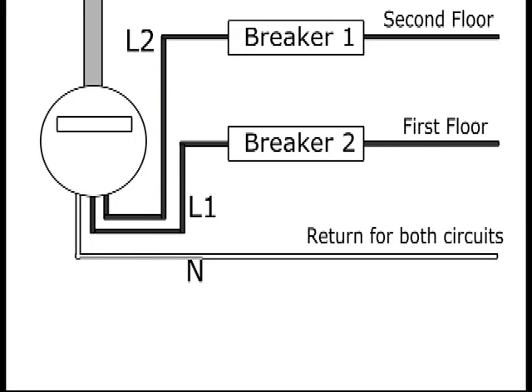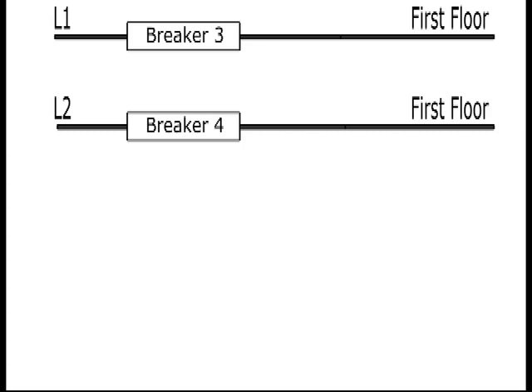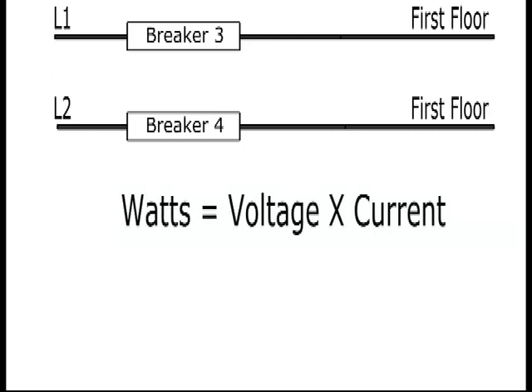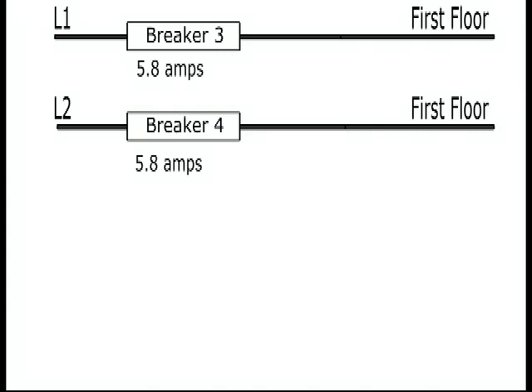On the other hand, if we have 220 volt service, we can add a couple of additional lines and breakers which carry 220 volts power to three special 220 volt outlets. So we can connect three 1270 watt heaters, but this time we will use heaters rated at 220 volts. Since they work with almost twice the voltage, the current flowing through the cables and the breakers will be about one half. This is because the watts consumed are the result of multiplying the voltage applied by the current flowing. A 1270 watt heater designed to run at 127 volts will pull 10 amps, while a 1270 watt heater designed to run on 220 volts will pull 5.8 amps.